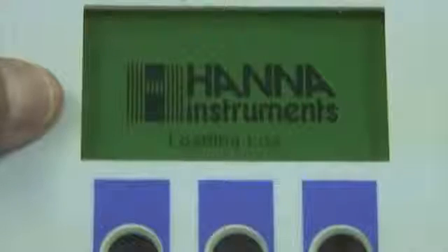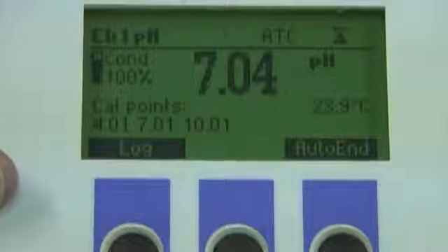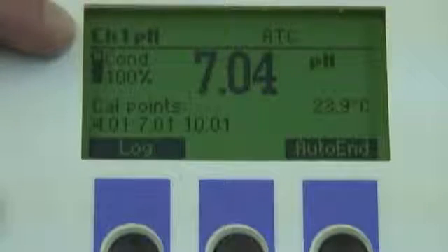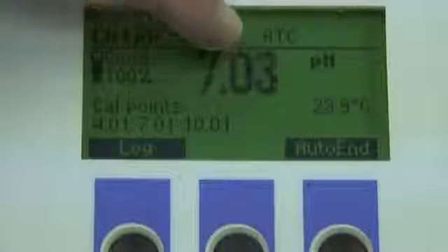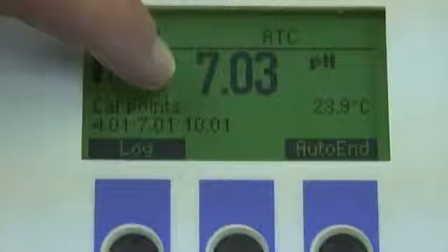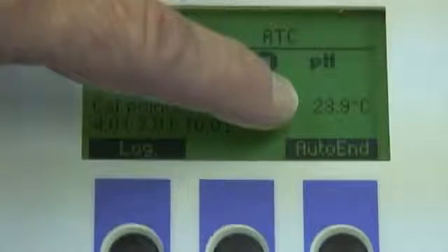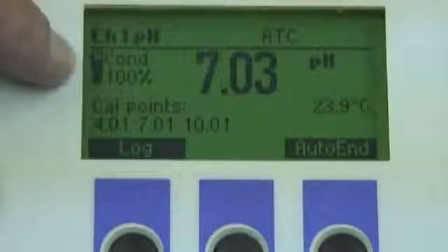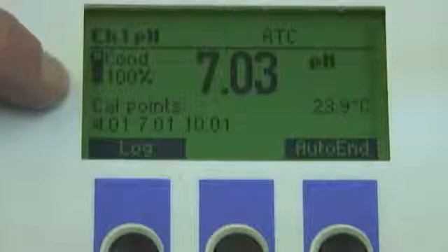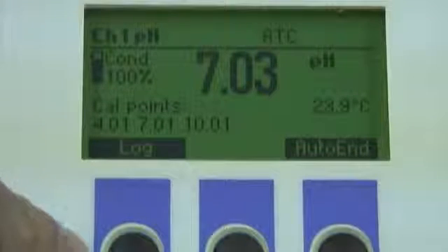Now I'm going to flip the meter on. And as you can see, it's warming up. And once the meter warms up, the LCD is going to display a lot of different information. Now let's take a look at what we're seeing. In this case, it's telling us that we're on channel 1, automatic temperature compensation. The solution that I'm measuring has a pH of 7.03 with a temperature reading of 23.9 degrees Celsius. A really great feature with this meter is that I can actually see the condition of the probe after calibration. In this case, it's telling me that it's at 100%, and I've calibrated with buffers of 4, 7, and 10. If I want to record the current reading, I simply hit the log button.